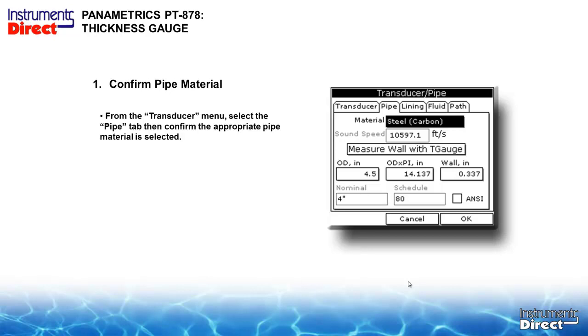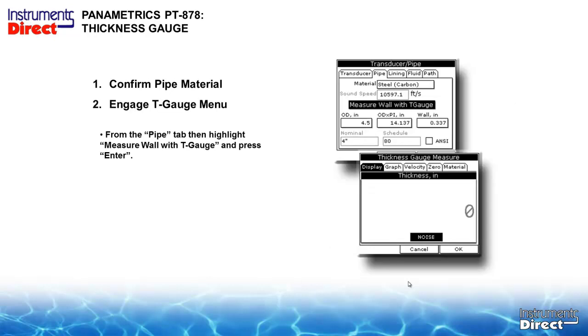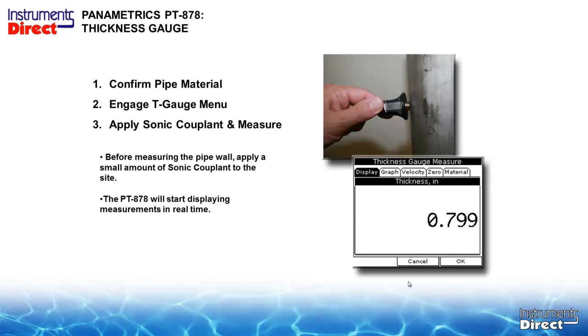So from the transducer menu, select the Pipe tab and then confirm the appropriate pipe material is selected. And from the Pipe tab, then highlight Measure Wall with the T gauge and then press Enter. As we said, apply the acoustic couplant. In this case, it's glycerin. You need to press firmly on the pipe or metal or whatever you're measuring. And then the PT878 will start displaying measurement in real time.